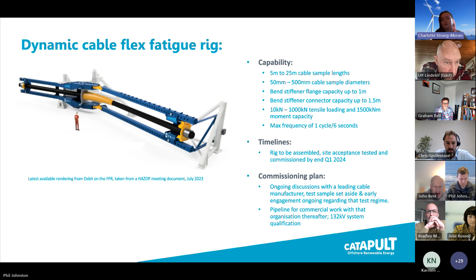So for those of you on the call who are perhaps new to intra-array cables, I wanted to set the scene. Intra-array cables for both fixed and floating wind farms are AC three-phase cables connected in circuits that can be in loops or individual strings, making up your collector grid. Intra-array cables can cost up to £35 million for a 1 gigawatt fixed wind farm, and these costs will rise when looking to floating offshore wind farms. The industry started with large-scale farms using 33 kV. We're now seeing 66 kV as our go-to level, but we'll be seeing in the future, in the current pipeline, qualification of 132 kV as well.